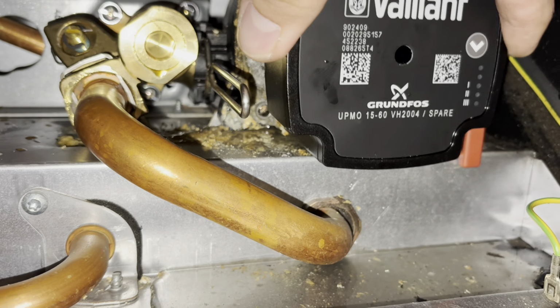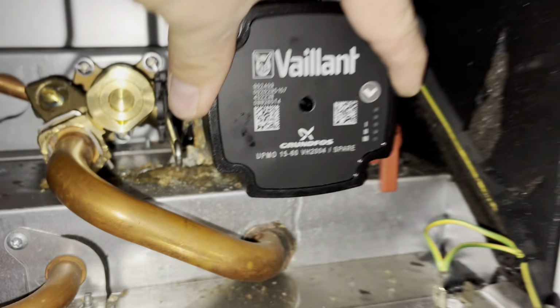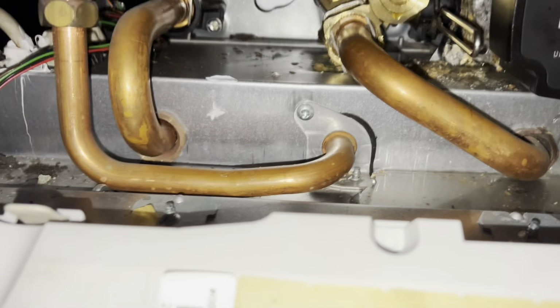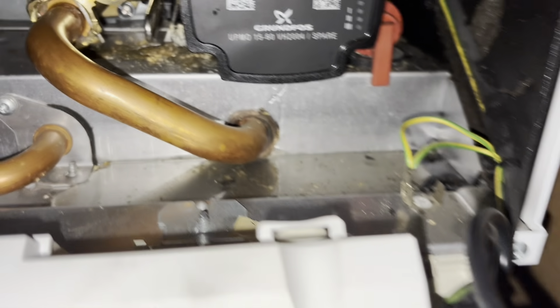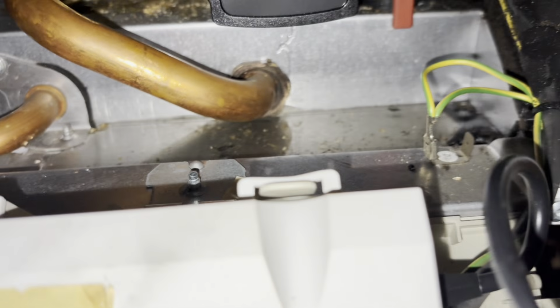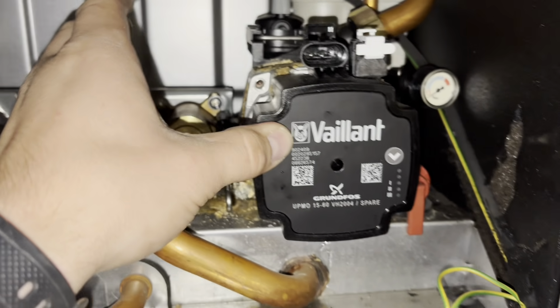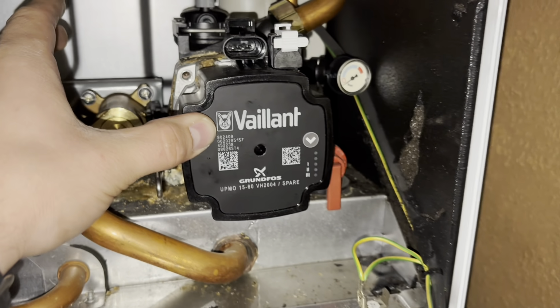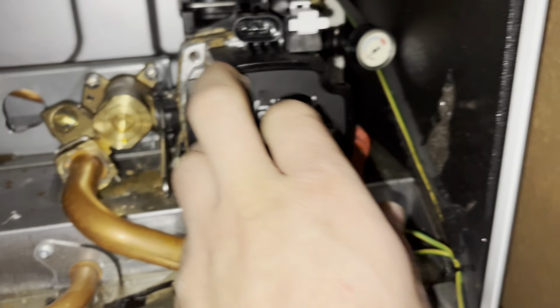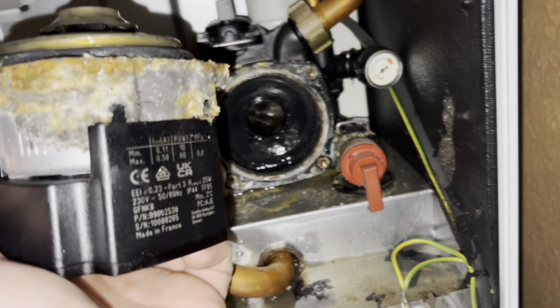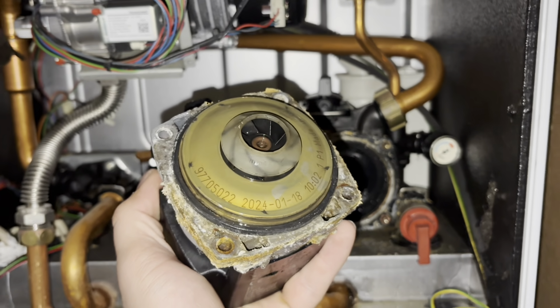So I've got quite a bit of residual water inside the system, as you can tell. I'm hoping this bag underneath will catch anything that leaks from the boiler. It covers the whole area of the bottom of this little shelf inside the boiler, so I'm just gonna go for the change quickly. Right, most of the water's here. I'll dry that up in a minute. Remove the pump head.